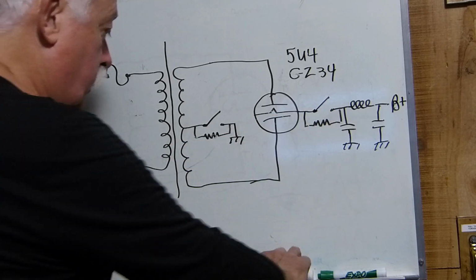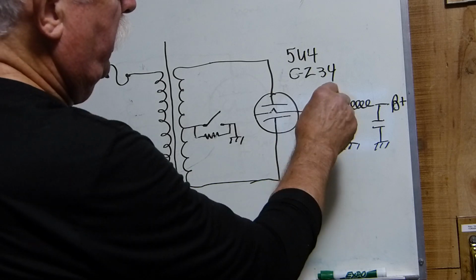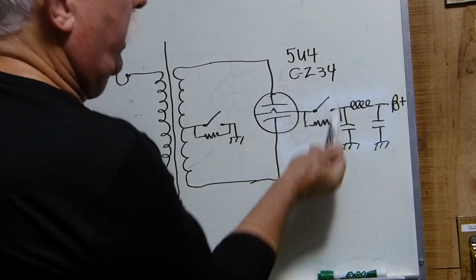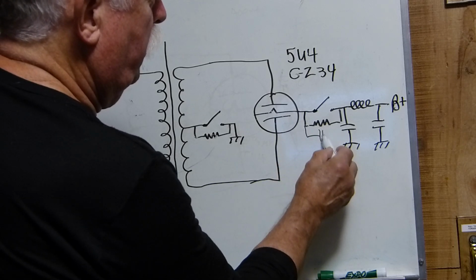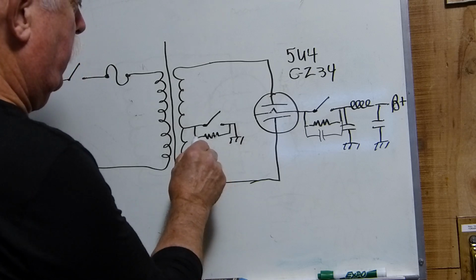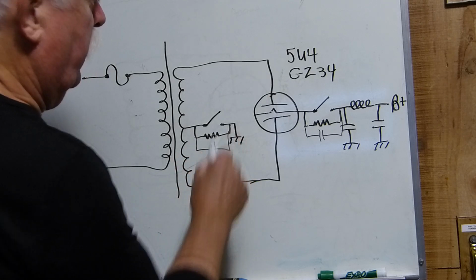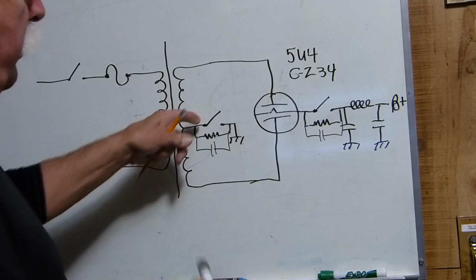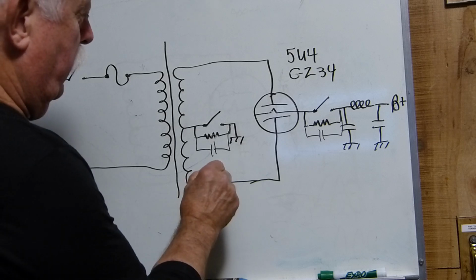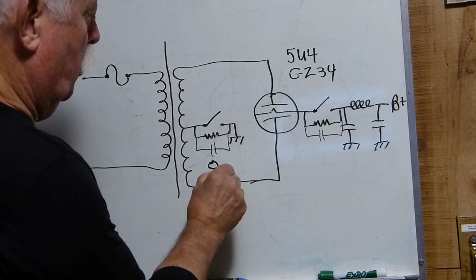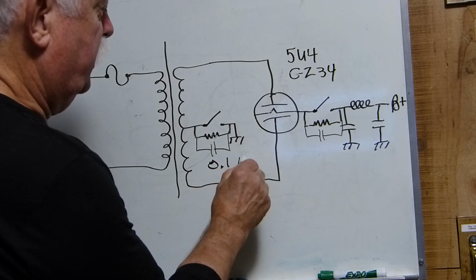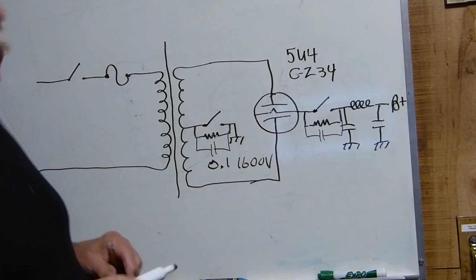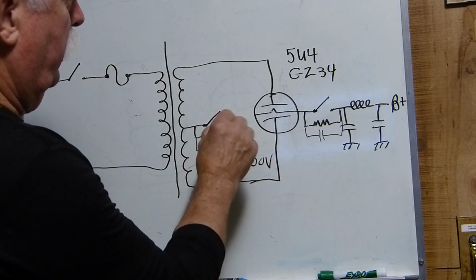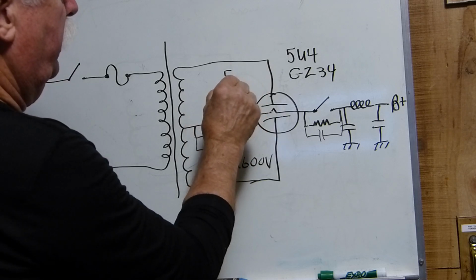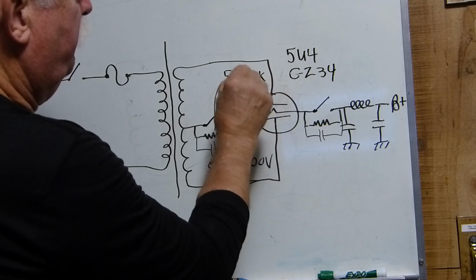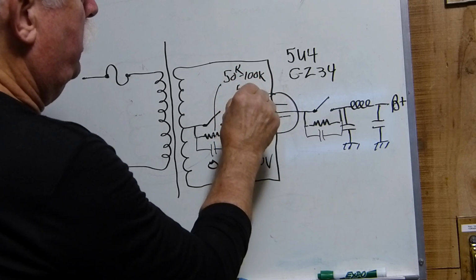You could also, to help extinguish the spark across it when these contacts open, put a little capacitor across it too, something like 0.1 microfarad. It's got to be rated at quite a high voltage, because there's going to be a big spike there. Maybe something like a 0.1 at 1600 volts, a high voltage capacitor. And like I say, that resistor right there, I would make it somewhere between 50K and 100K, at least 5 watts.